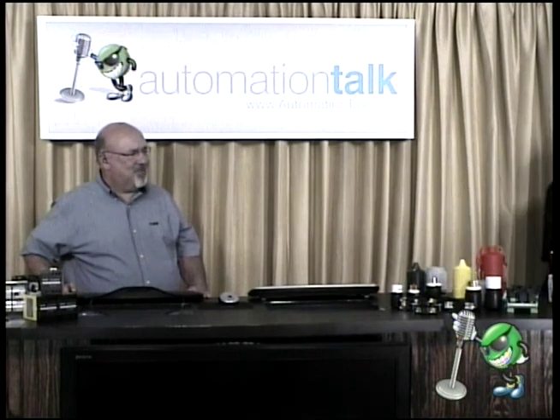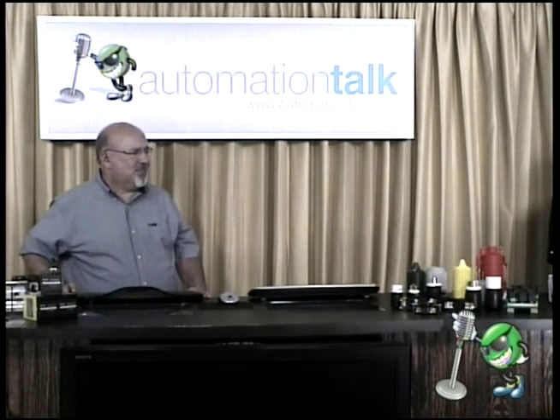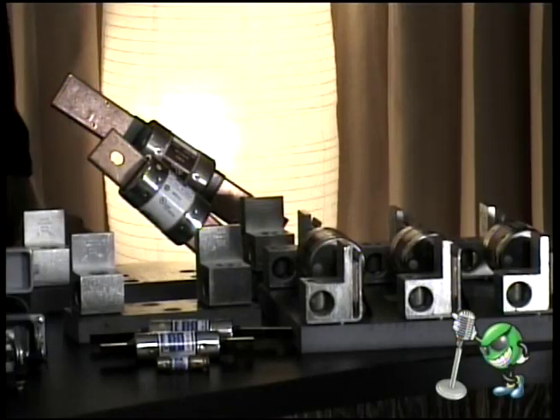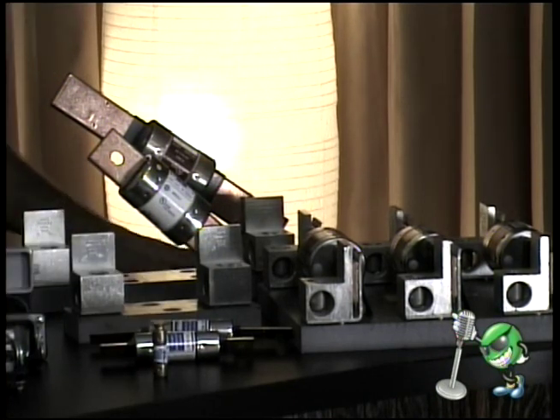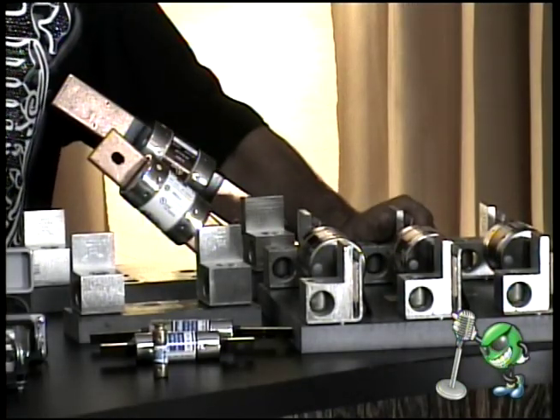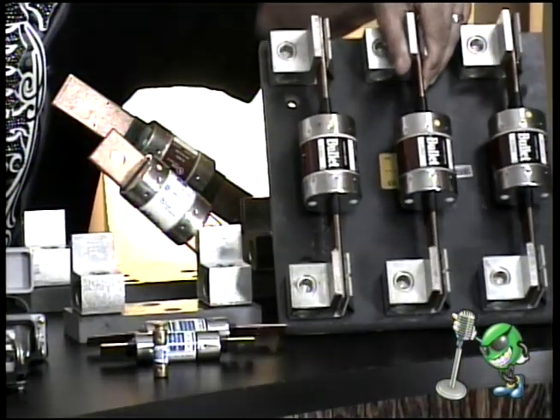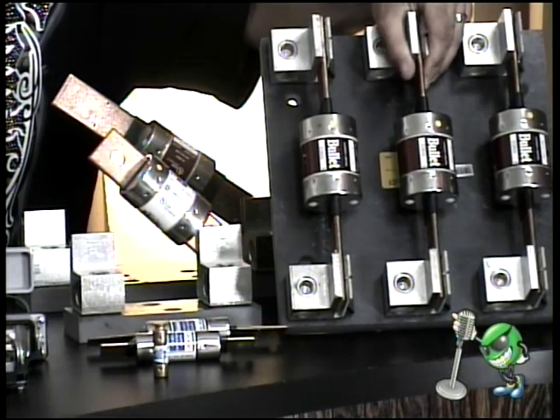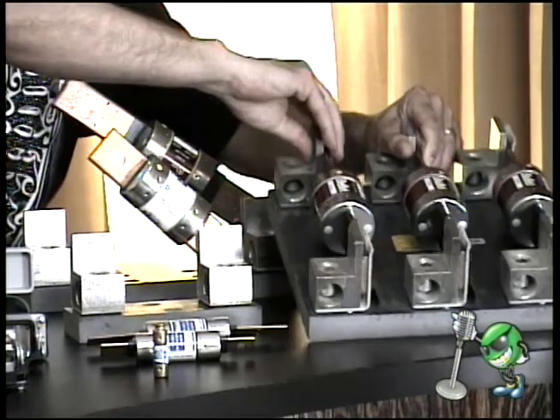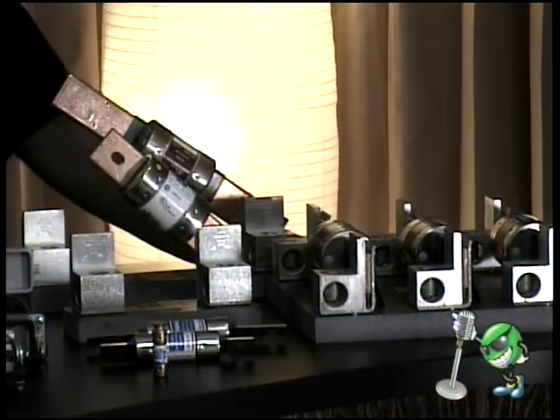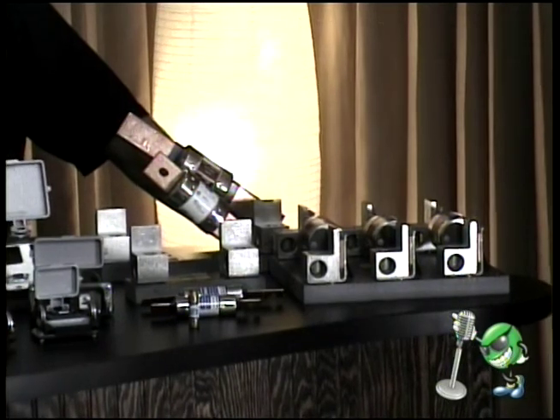Our last category is fuses and fuse holders. I guess the biggest thing I can say there is they're big, but they're small too. We go all the way from the 5 by 20 millimeter glass types to the 1/4 by 1.25 glass type fuses, to the ceramics, all the way up to the big knife blade type fuses, the RK5s, and Class J. Class CC is the small cartridge type fuses that you're going to find on transformers and in some cases for motor protection.